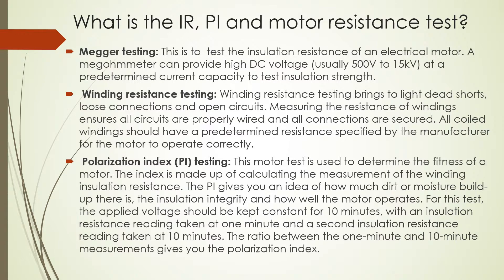The second question: what is the IR, PI, and resistance test for a motor? IR means megger testing — this is done to test the insulation resistance of an electrical motor. A megger meter can provide high voltage DC, usually 500 V to 15 kV, at a predetermined current capacity to test the motor insulation strength.